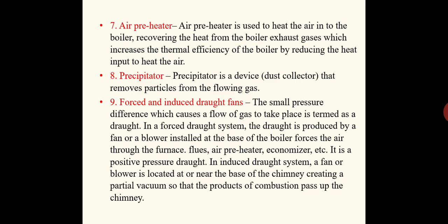Sometimes the fan will be provided at the bottom of the boiler itself, then it is called forced draught fans. If the fan is provided at the bottom of the chimney, then it is called induced draught. The function is that, if the fan is provided at the bottom of the chimney, flue gas is sucked from the boiler side and passed through the chimney.